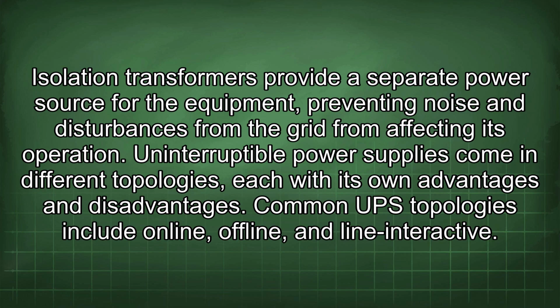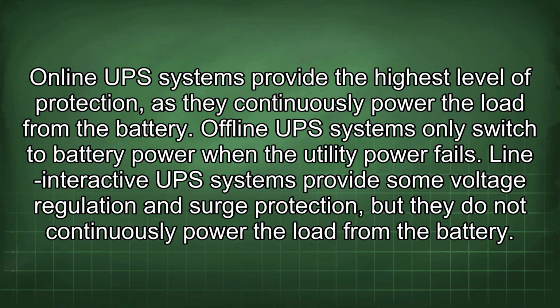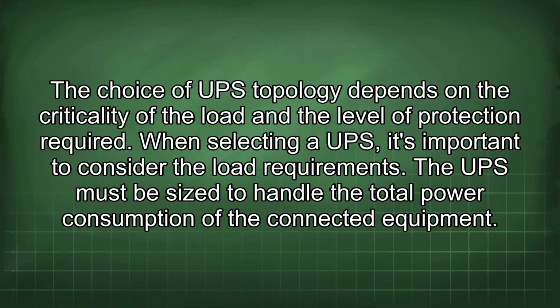Common UPS topologies include online, offline, and line interactive. Online UPS systems provide the highest level of protection, as they continuously power the load from the battery. Offline UPS systems only switch to battery power when the utility power fails. Line interactive UPS systems provide some voltage regulation and surge protection, but they do not continuously power the load from the battery. The choice of UPS topology depends on the criticality of the load and the level of protection required.